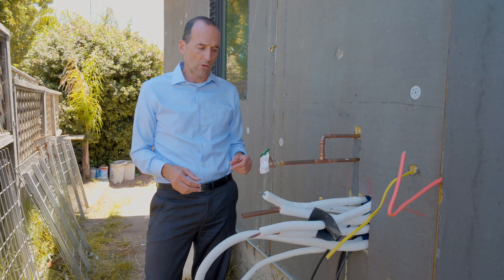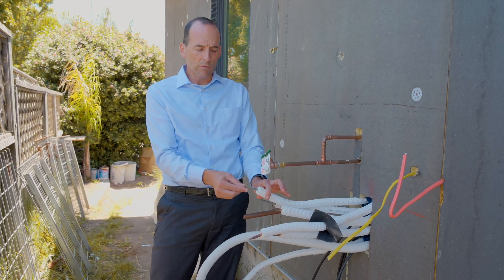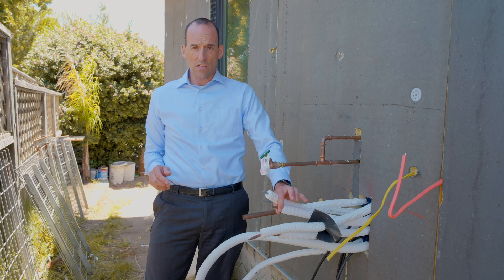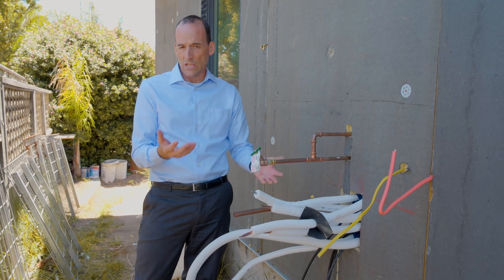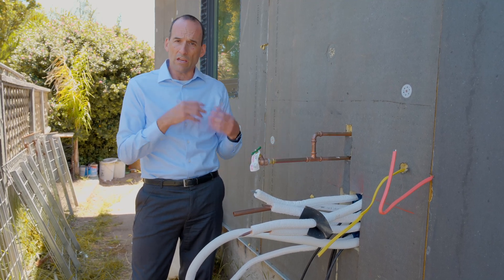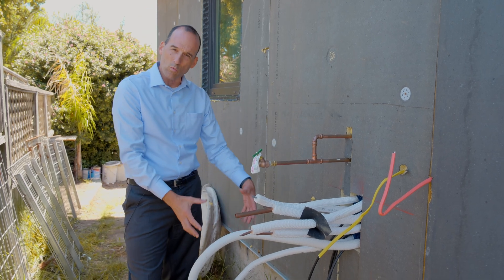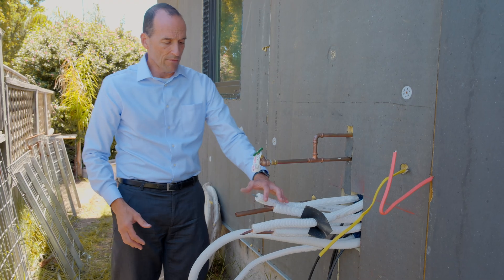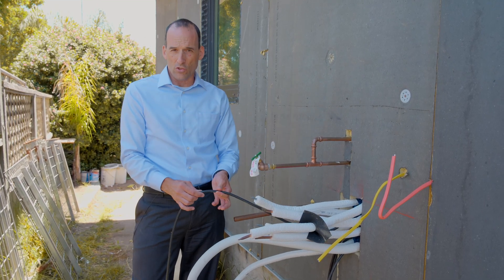Now we're outside at the place where our heat pump is going to be located. All of these line sets — there are eight different line sets, and each one is paired with a liquid refrigerant line and a gas refrigerant line. One goes in and one goes out, and that's how they transfer heat from the heat pump unit, which sits outside on the ground, into those individual units that heat and cool those spaces. Those individual units are individually controlled and in different zones, so one can be heating and all the rest can be off. All of these copper lines go down to one individual outdoor unit — so we don't have four independent units, we have one unit that controls all four, each with their own line set, drain, and control line.